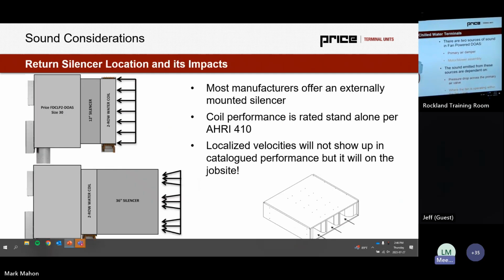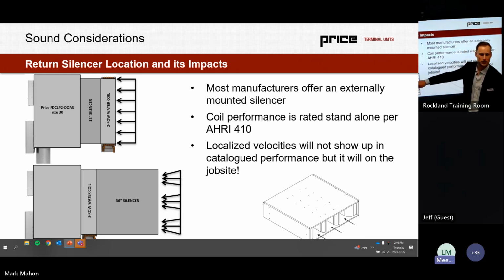So what we need is something to stop sound but allow for air to travel. And for us, that is a silencer, and in this case, an integral silencer. What we have up top is our version of this product versus a rough sketched out depiction of a competitor's product. The difference here is silencer position with respect to the coil. And if we actually have the silencer on the outside of the coil, it won't show up in the catalog, but it can lead to localized velocities that will cut the effective surface area of the coil and reduce capacity.